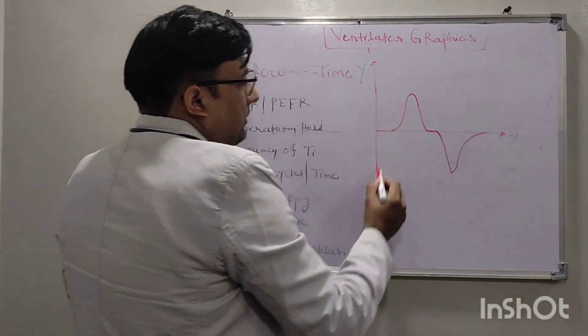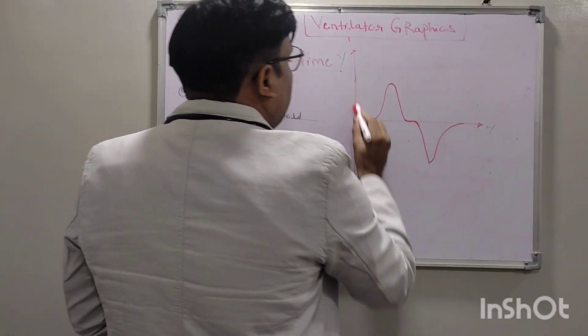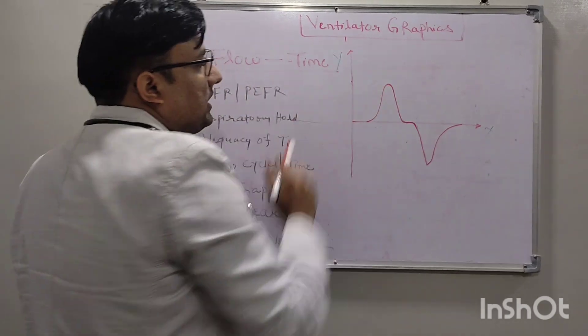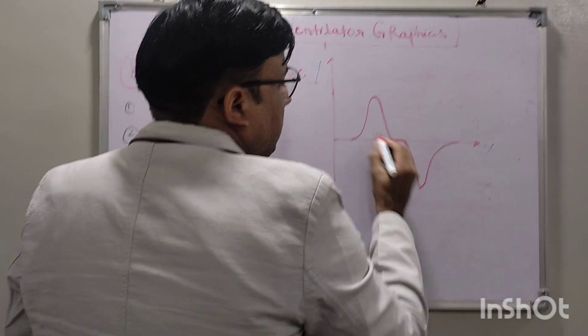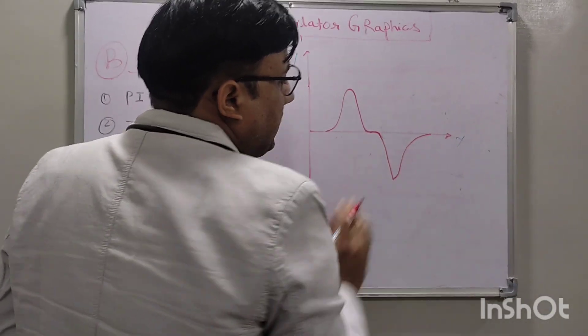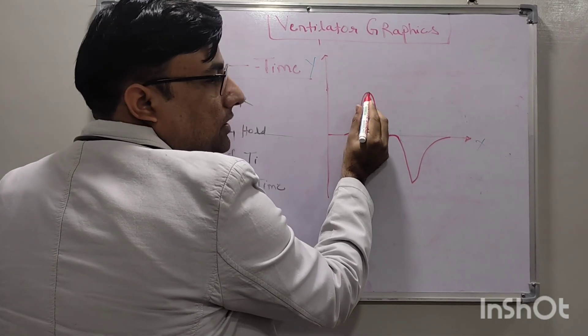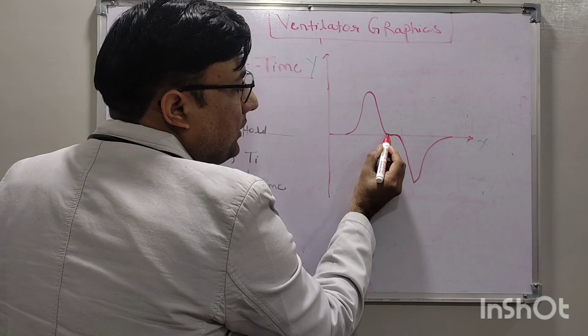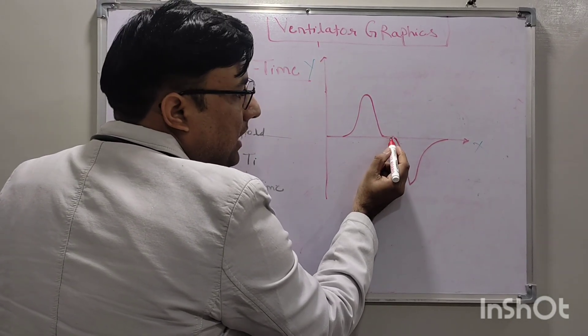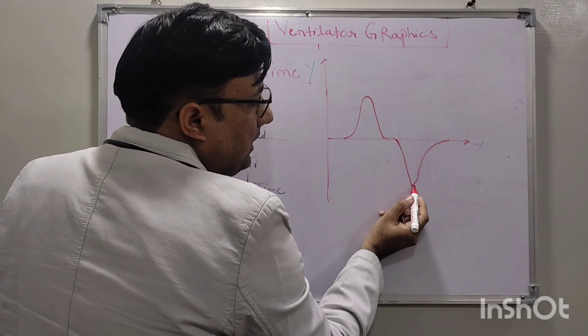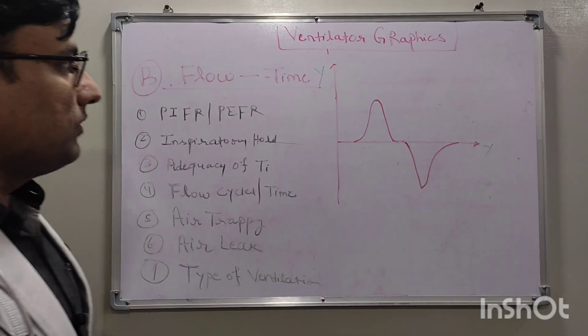In the flow-time curve, the x-axis is time in seconds and the y-axis is flow in liters per minute. Above the baseline on the positive side is inspiratory flow; the negative side is expiratory flow. Inspiration starts, flow increases to the peak flow, then decreases, coming to the baseline. There will be an inspiratory hold during the inspiratory time, then expiration starts — going negative and returning to the baseline. This is the full flow-time curve.